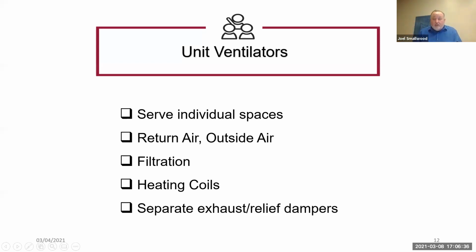They're typically a vent in the ceiling that has, some have fans in them, some don't, but they actually pull air out of the room and they are tied to that unit ventilator. So the unit ventilator adjusts how much air they're bringing in, just like the big systems do, the minimum outside air. And at the same time, that exhaust air damper is moving with it to allow air to move out of the space as well.